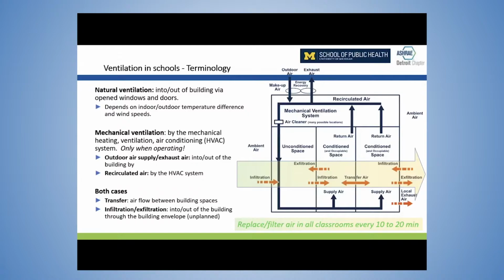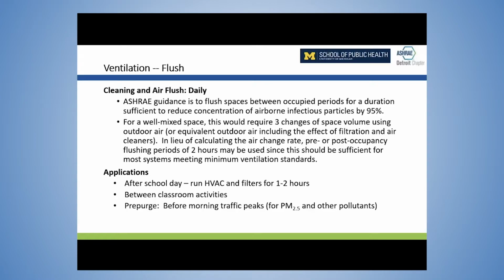There are additional ways to use ventilation to improve the air quality, reduce COVID, and so forth. There are flushing procedures where the space can be unoccupied and the space is flushed by changing the air quite rapidly. I don't see a lot of schools do this, but there are a number of good applications, both after the school day, between classroom activities, and as a pre-purge, in particular before morning traffic peak, which might bring in pollutants. You can pre-purge before that and condition the space.